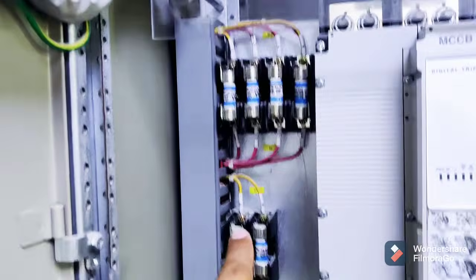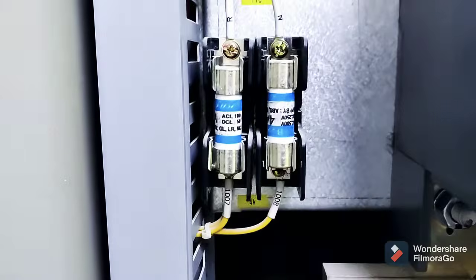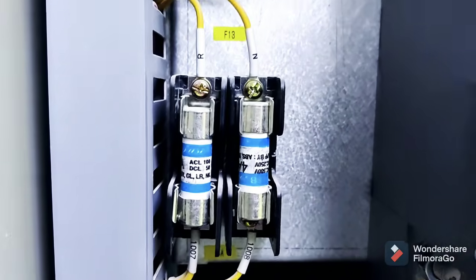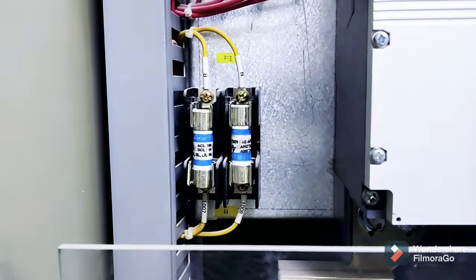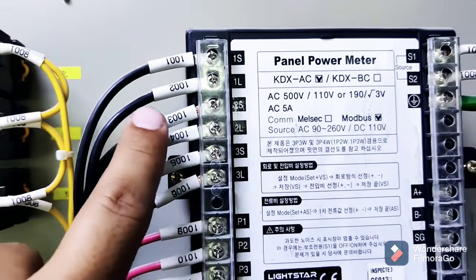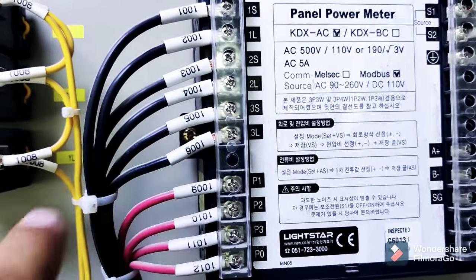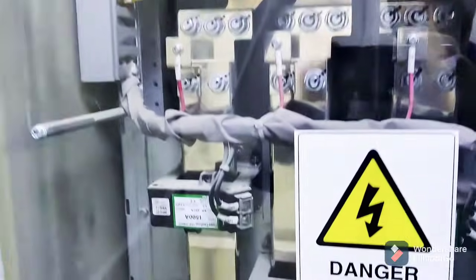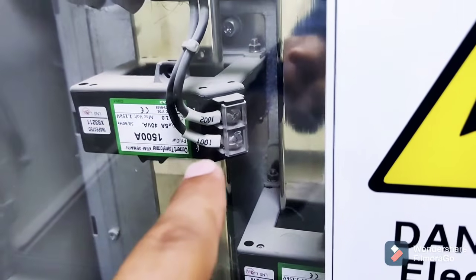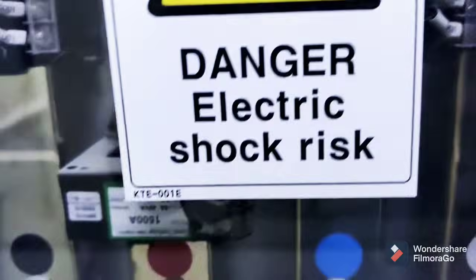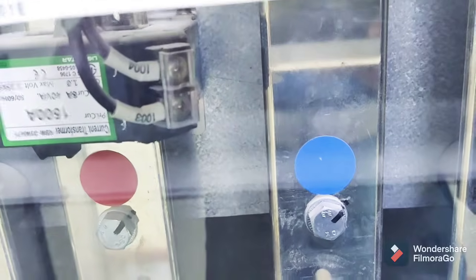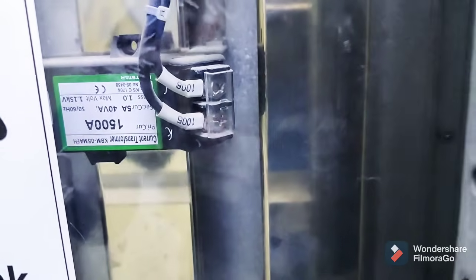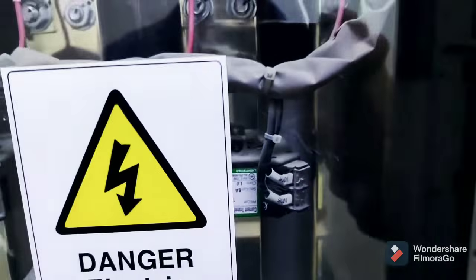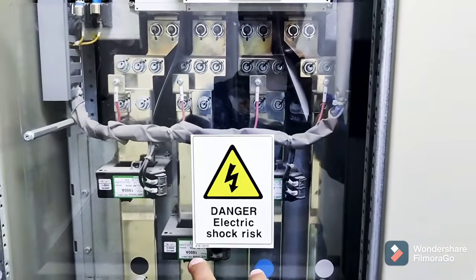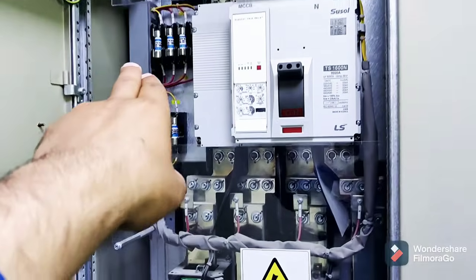See this power supply from the top to here, you can see the numbers 1007, 1008. We gave the tag numbers. This is connected with the 4 ampere fuse from the supply. So 1001, 1002, 1003, 4, 5, 6. All this connection you need to do with the CT, current transformer. 1001, 1002 connected to this current transformer, and 1003, 1004 connected to the other current transformer, like the other line. We have 3 lines, the power supply lines. The other one, 1005, 1006, is connected here. So 3 current transformers we need to connect like this.